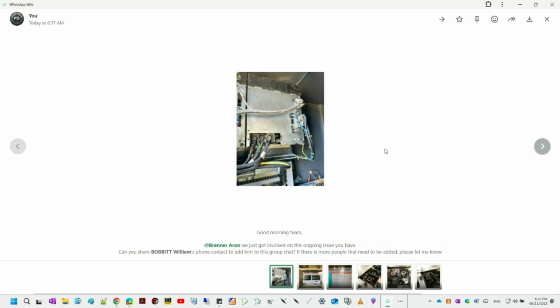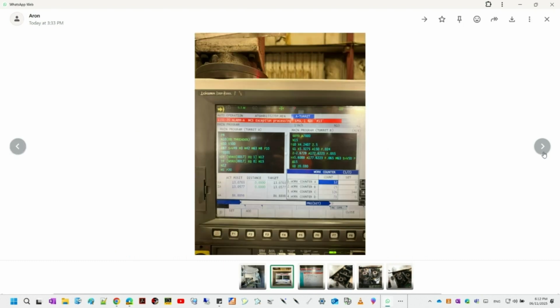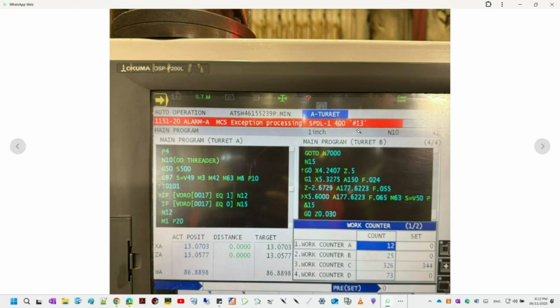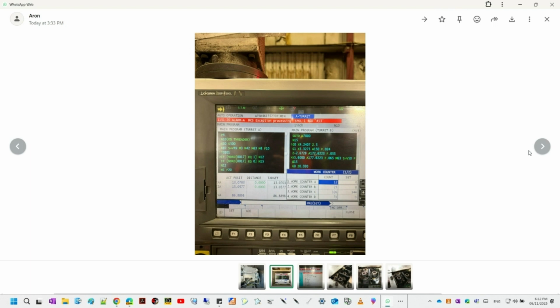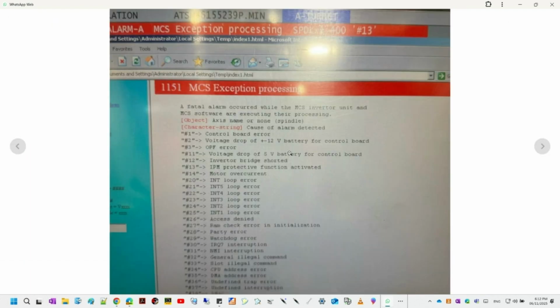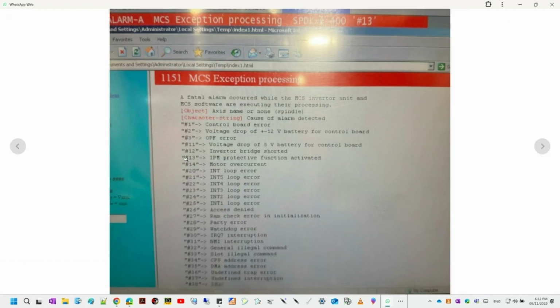Okay, now here's where the picture evidence gets really interesting, right? It tells the visual story. Looking at those photos of the damaged drive, what did they actually reveal? Oh, yeah. The visual analysis of the pictures was absolutely key to pinpointing the probable cause. Several things jumped out immediately. You saw significant discoloration and soot all around the terminals, especially bad on the U and V phase terminals. That indicates intense heat, maybe even some combustion or electrical arcing.